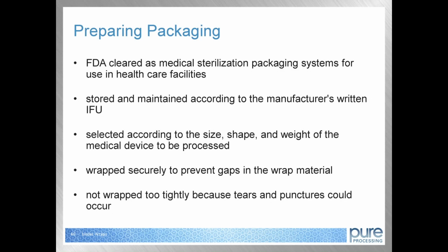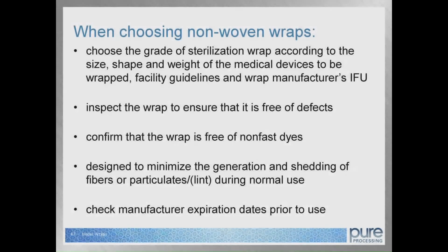Additionally, ANSI AAMI ST79 recommends that woven and non-woven wraps should be FDA cleared as medical sterilization packaging systems for use in healthcare facilities. They should be stored and maintained according to the manufacturer's written IFU and selected according to the size, shape, and weight of the medical device to be processed. Items should be wrapped securely to prevent gaps in the wrap material, and items should not be wrapped too tightly because tears and punctures could occur. Once packaging materials have been chosen and implemented within a facility, the preparation of items for sterilization begins after decontamination.